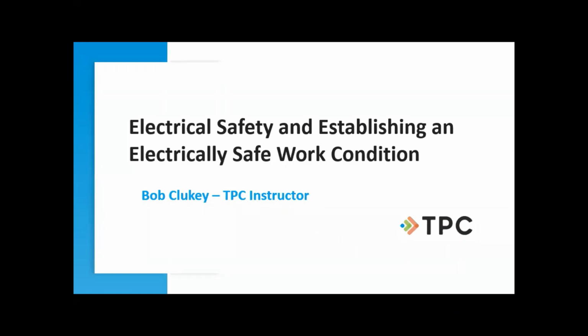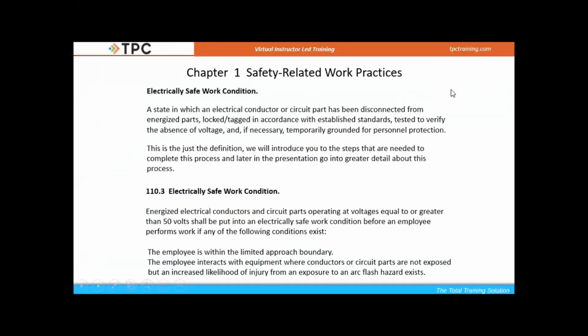So this, of course, is all based on OSHA 1910 and NFPA 70E. So we will take a look at what they have inside this document. This came from Chapter 1 in NFPA 70E, and it gives us a definition of the electrically safe work condition. So it's going to be a state, right? And that state is going to be when we have been disconnected from all energized parts. And then we lock and tag it out in accordance with your policy, because OSHA just says this.